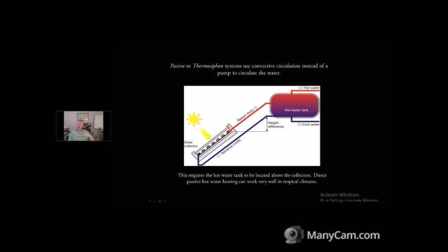Very simple. So if you're in the tropics near the equatorial region and you don't have a problem with freezing and you got a lot of sun year-round, then this system—a passive or thermosyphon system direct with flat plate—is probably going to work really well for you.